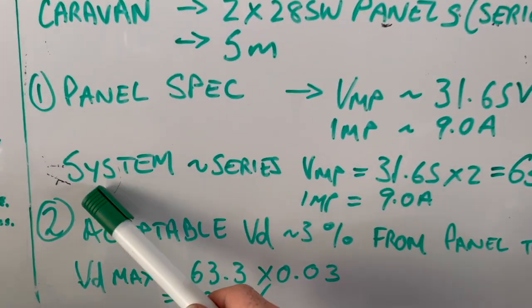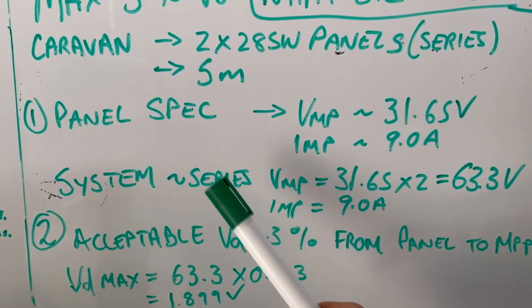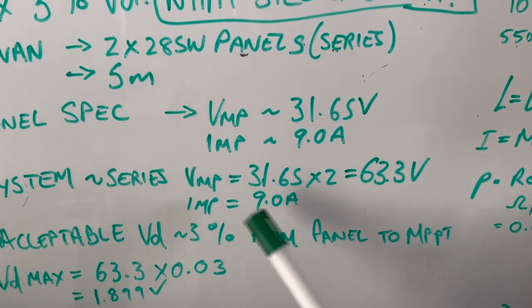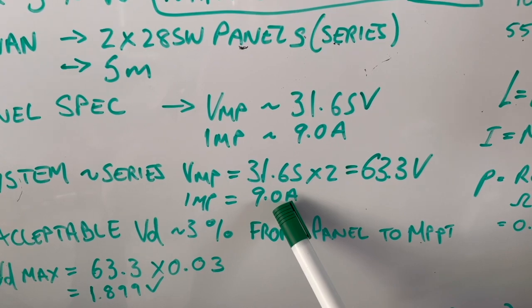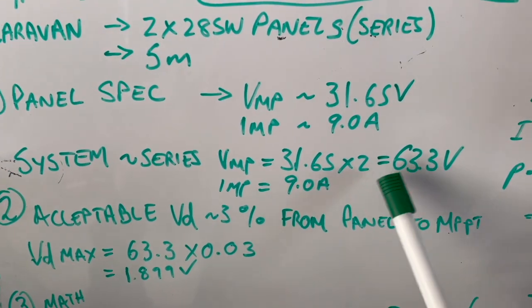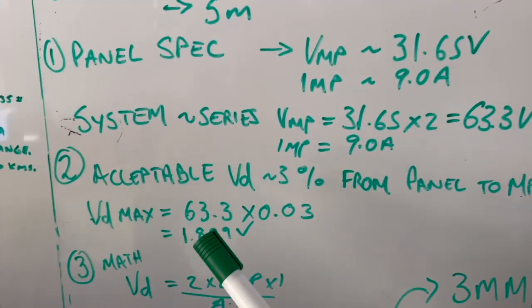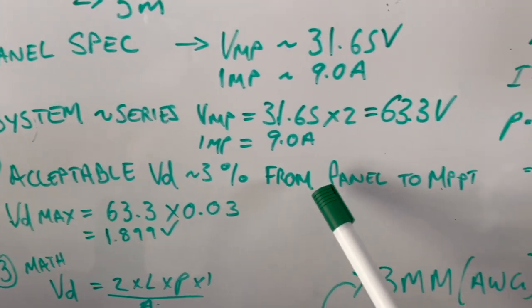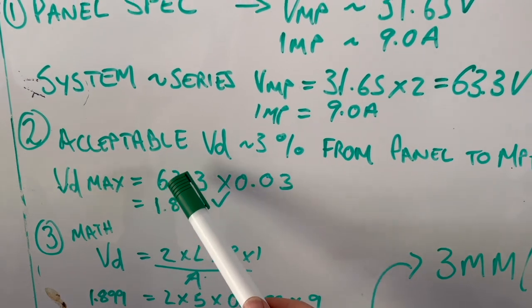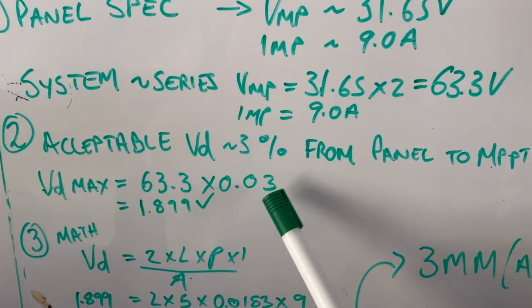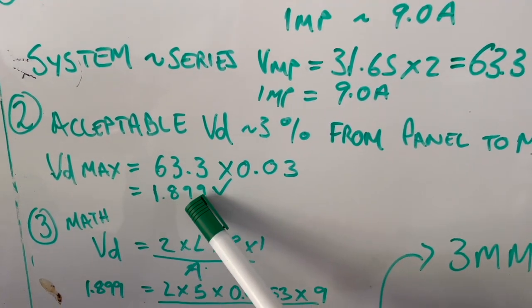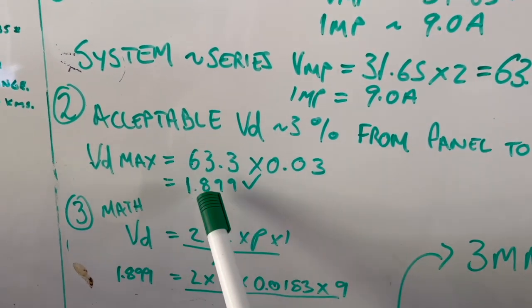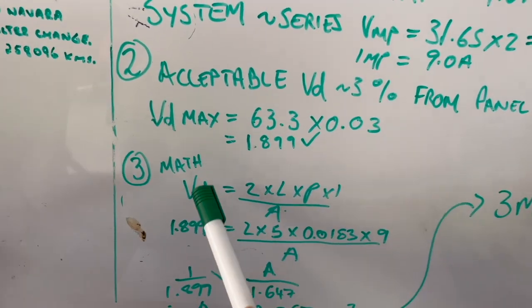So you work out your system information now. They're in series, VMP times by 2, 63.3 volts, IMP is 9 amps. That stays the same. We work out now what an acceptable voltage drop is. So we've said it's 3% from panel to MPPT, so 63.3 times by 0.03 equals 1.899 volt. So that is how much voltage drop we can accept.